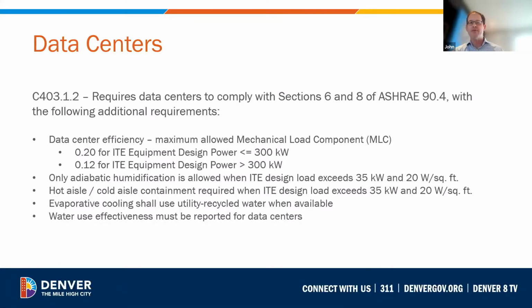The mechanical load component, or MLC, which is the ratio of energy consumed by the HVAC systems to the facility energy consumption, is set at 0.20 for design power at or below 300 kilowatts, and is set to an even lower value of 0.12 for larger data centers with an IT equipment load over 300 kilowatts. That would apply to most medium to large size data centers.